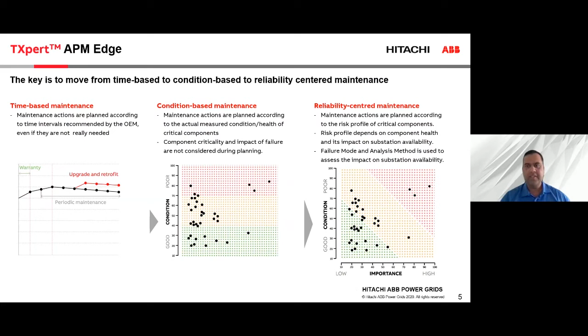So when I talk about APM Edge, we start with the nameplate data. If you have the heat run test data, we take that into account. We require data for bushings, for tap changers, DGA results, standard oil test results, and inspections. Sometimes when you do transformer inspections, you have data which is not quantified: oil leaks, paint flaking, dirt on the bushing. All of that can now be part of APM Edge.